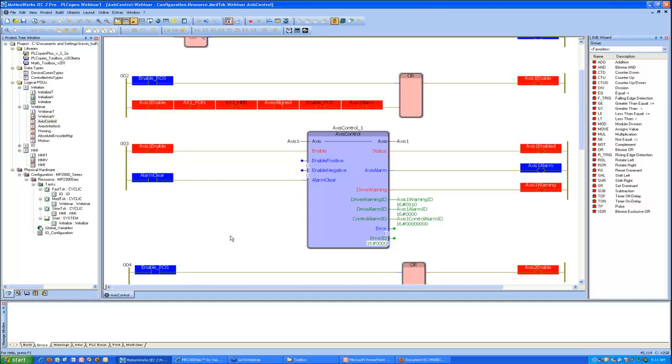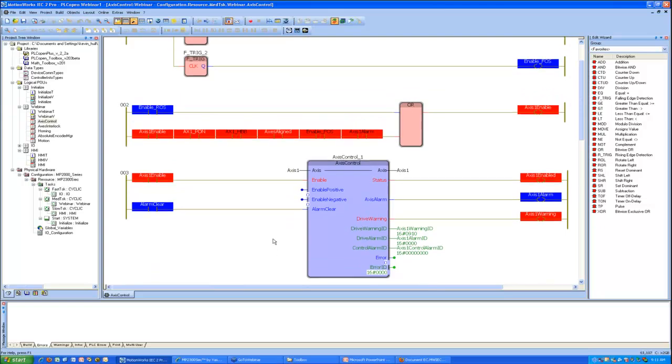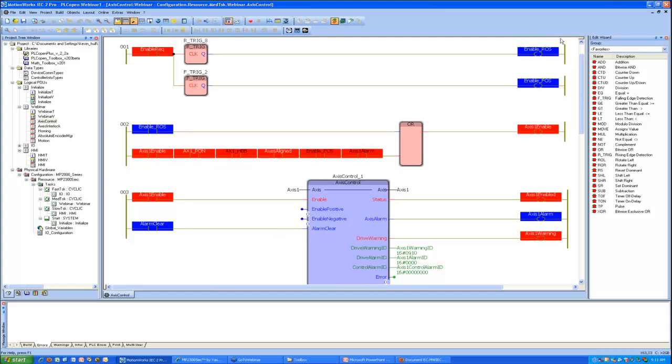And so I'm demonstrating some of the other surrounding interlock logic that's useful for enabling the servo. So I've got some one-shots here that will enable or disable when I change the enable request. And then my logic will keep the axis enabled as long as the power is on. This is a global status bit. And as long as the hardware base block is not on, that's the safety circuit, the CN8 on the SGDV. And a couple other things I'll talk about with other function blocks I'm describing later on.